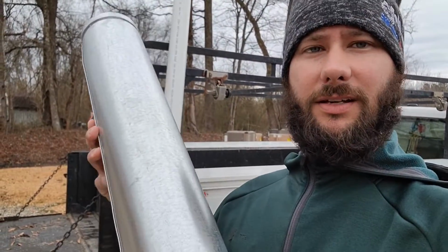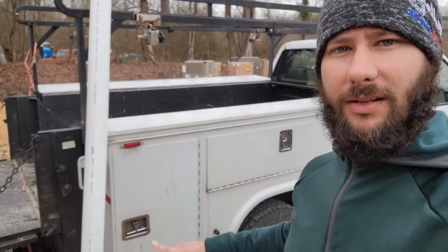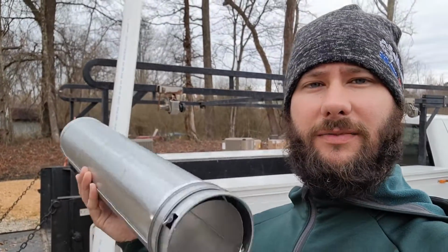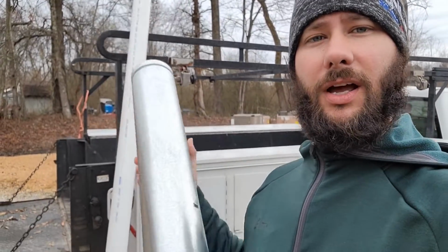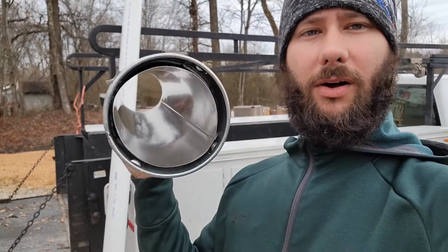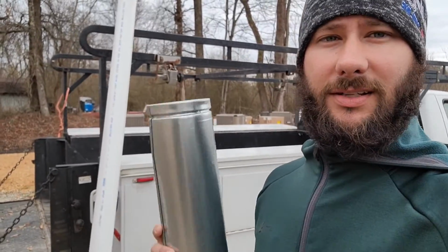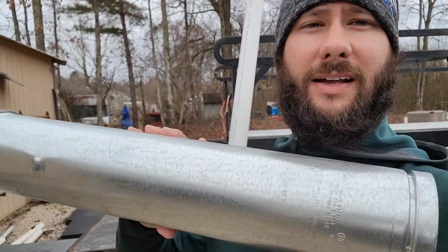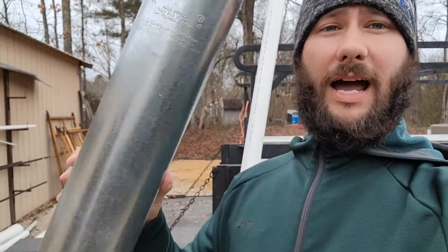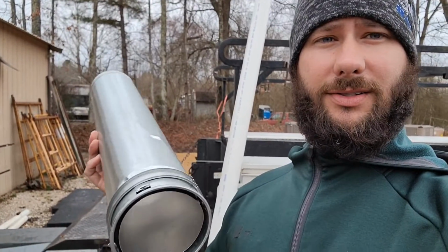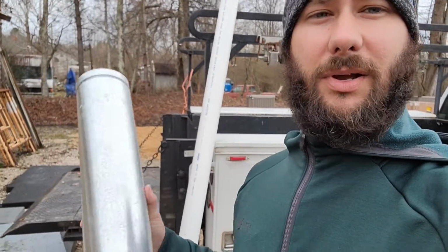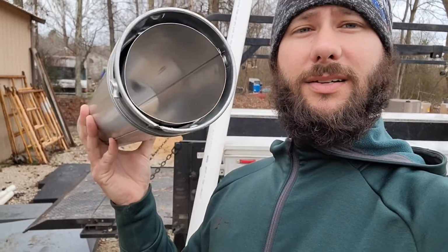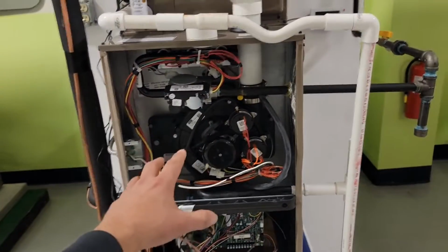So a cost comparison between double wall type B venting used for 80% furnaces and this Schedule 40 3-inch PVC pipe: if you want to make up 10 foot of either one of these pieces of pipe, this double wall type B vent is actually going to be double the price. This 10-foot stick is about $50 for that Schedule 40 3-inch PVC for a 90% furnace, and for about 5 foot of this type of vent pipe, it's about $80 to $100. So I want to give you an idea of what the cost comparison is between the two types of venting material.